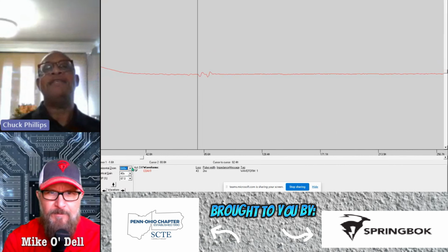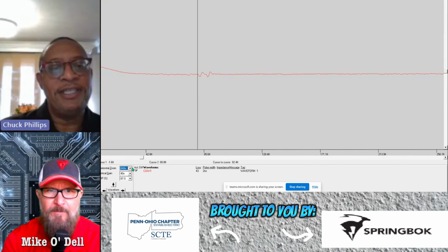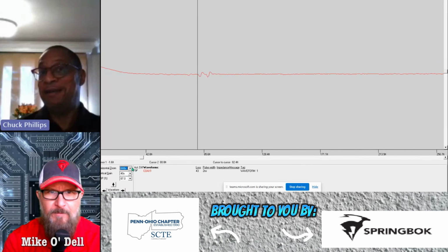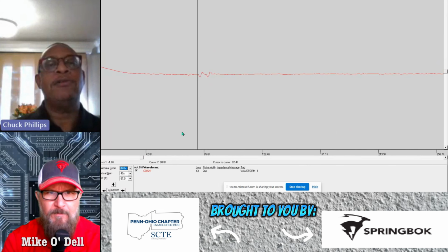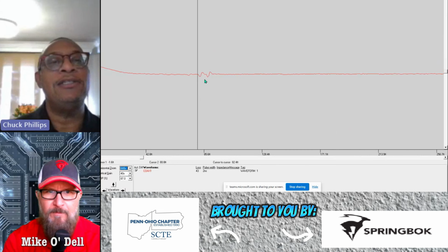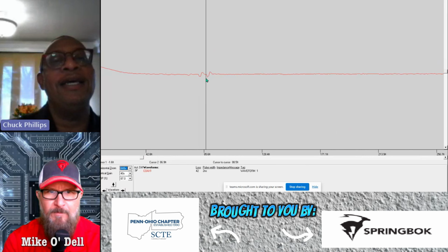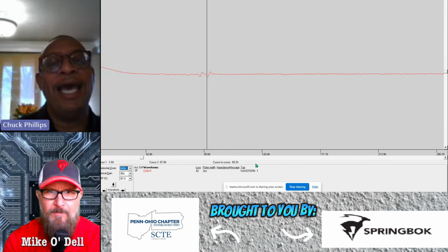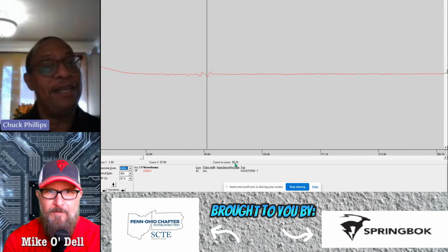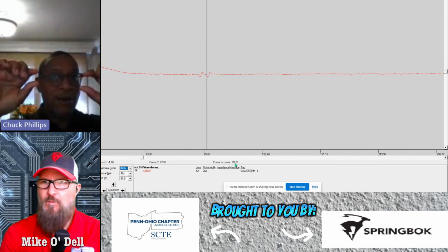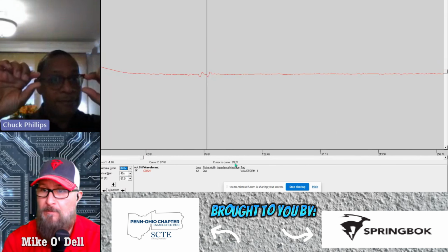Yeah, and the reason I have to say very likely is because different TDRs have different programs that display it differently. But on this particular TDR, I shot this, so I know what it is. And by the way, this is two separate events. The first one is at 82.4 feet. The second one is at 89.2 feet. Now, let me tell you what this happened to be. This happened to be two dings in the hardline cable, just two dimples.